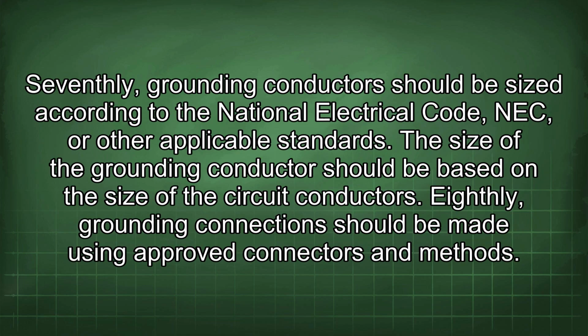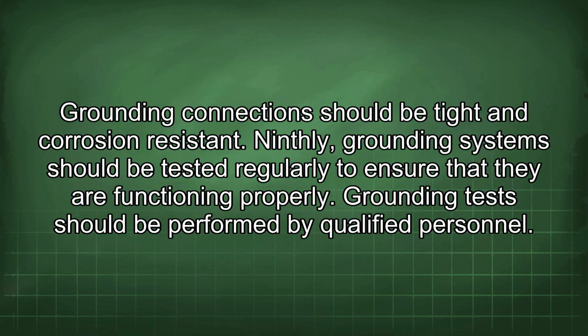Seventhly, grounding conductors should be sized according to the National Electrical Code, NEC, or other applicable standards. The size of the grounding conductor should be based on the size of the circuit conductors. Eighthly, grounding connections should be made using approved connectors and methods. Grounding connections should be tight and corrosion resistant. Ninthly, grounding systems should be tested regularly to ensure that they are functioning properly. Grounding tests should be performed by qualified personnel.